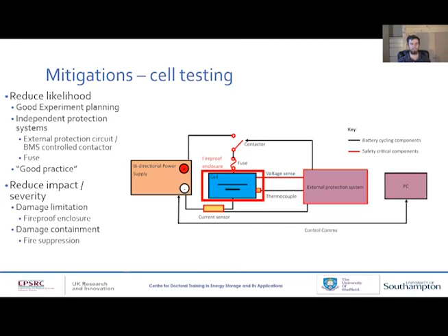Okay, looking back to those system diagrams, firstly for the single cell, this is what the new system diagram is if you're implementing all of those mitigations. We've got our fuse and contactor, which is being controlled by this external protection system, and that system is measuring temperature, voltage, and current.